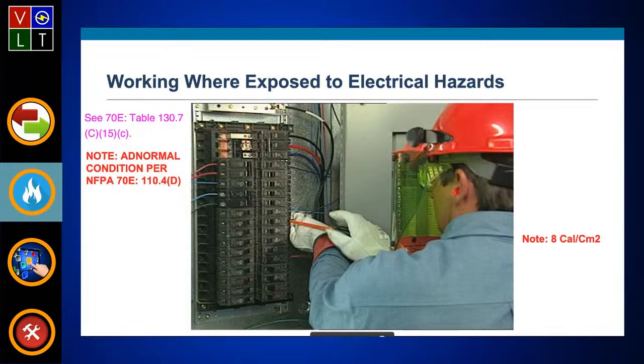There's a lot of confusion with this—that's why I wanted to ask. Some companies take the managed risk that if it's been maintained in accordance with 70B, the maintenance standard, they could remove a cover and go to table 130.5C, which would give you a no-PPE requirement. But not many companies will allow that.